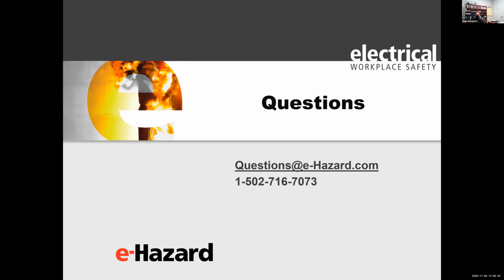So it's always a good idea to have some kind of label so at least there's some kind of warning, because even if people don't know what an electrical panel is, if it says warning, shock and arc flash hazard, basically this can kill you, that kind of helps keep people from opening that door. We had a guy who was putting his lunch inside of a switchgear in a nuclear power plant. He was a contractor and a construction person, didn't know anything about switchgear, but he was putting a metal lunch bucket, literally caught in an audit, putting a metal lunch bucket inside of a 13,800 volt switchgear. If he'd moved that bucket 2 inches back, it'd have blown that switchgear all to heck right in front of his face. And so our inspector stopped him, and from then on, that company locks the doors on there, and only the electricians and the supervisors have access to those rooms.